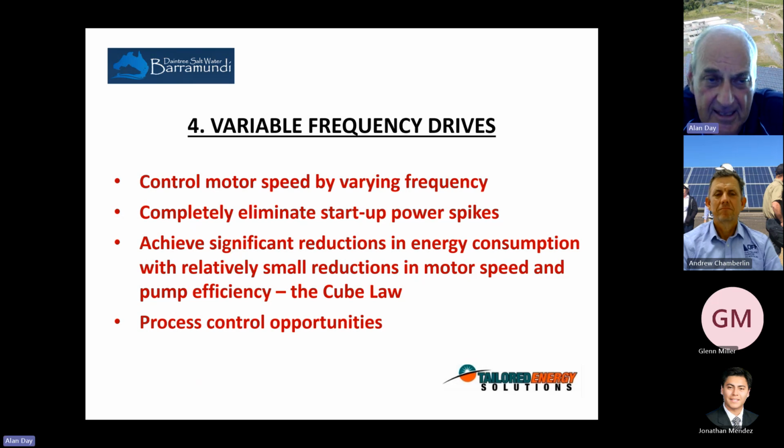The other thing, what we often end up doing these days, is using a variable speed drive as a really fancy soft starter and just a way to slow a pump down. The reality is they were invented originally to provide process control.